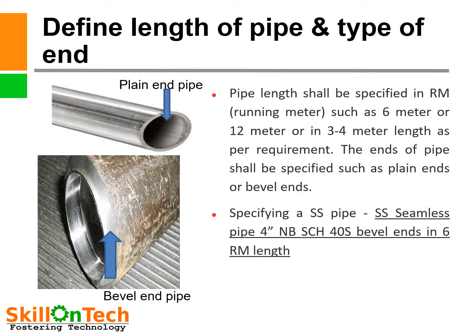Define length of pipe and type of end. A picture of a pipe with a plain end and another picture with a bevel end pipe are shown on the slide. We must specify the length of pipe in running meters — such as 6 meters, 12 meters, or 3 to 4 meters as per requirement. The ends of pipe shall be specified as plain ends or bevel ends. If we have to carry out welding of the pipeline, then we must procure bevel end pipes. For example, specifying a SS seamless pipe: 4 inch NB, schedule 40S, bevel ends, in 6 running meter length.